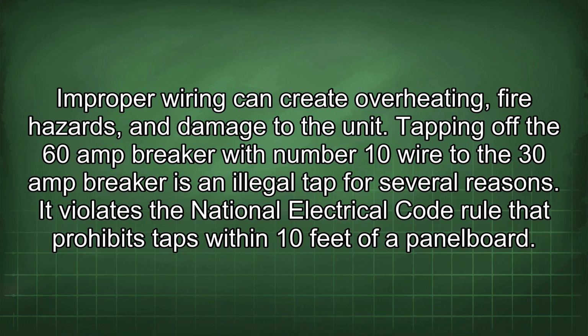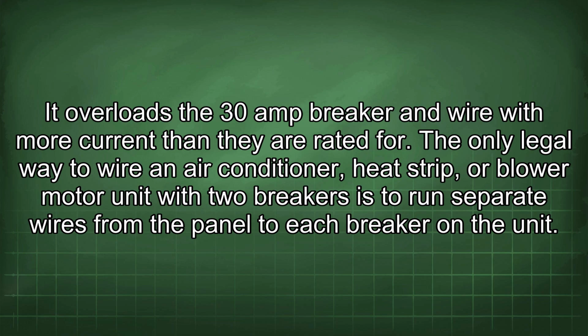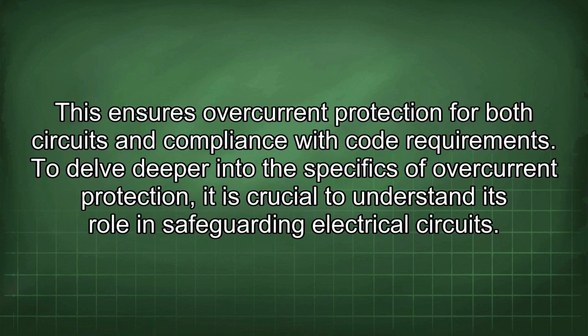Tapping off the 60-amp breaker with number 10 wire to the 30-amp breaker is an illegal tap for several reasons. It violates the National Electrical Code rule that prohibits taps within 10 feet of a panel board. It overloads the 30-amp breaker and wire with more current than they are rated for. The only legal way to wire an air conditioner heat strip or blower motor unit with two breakers is to run separate wires from the panel to each breaker on the unit. This ensures overcurrent protection for both circuits in compliance with code requirements.